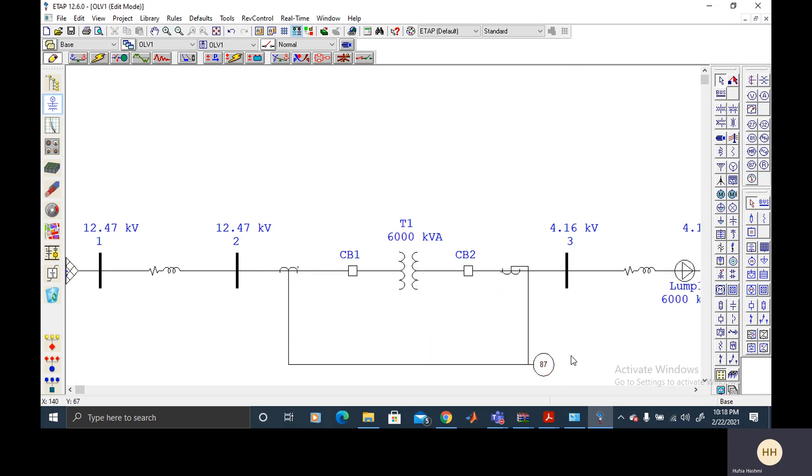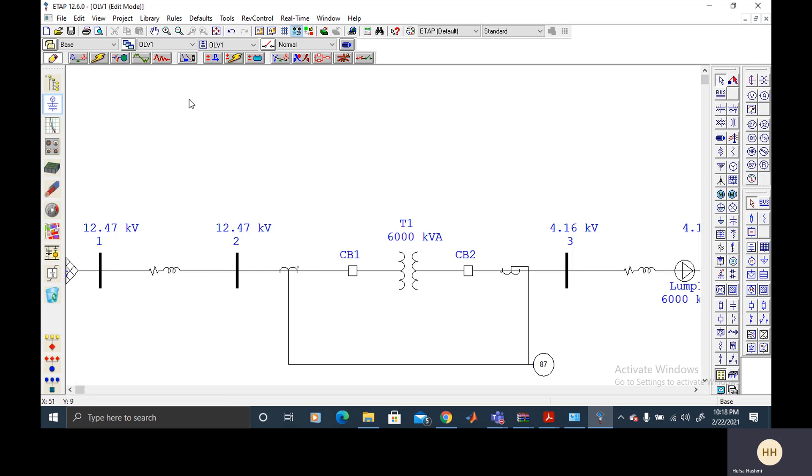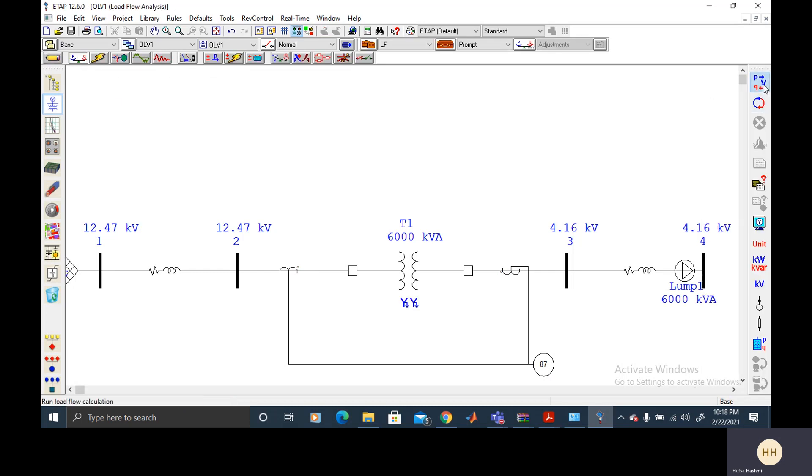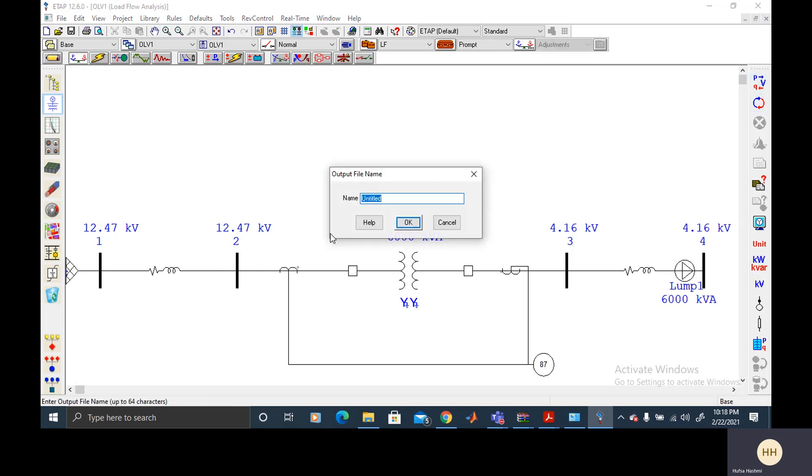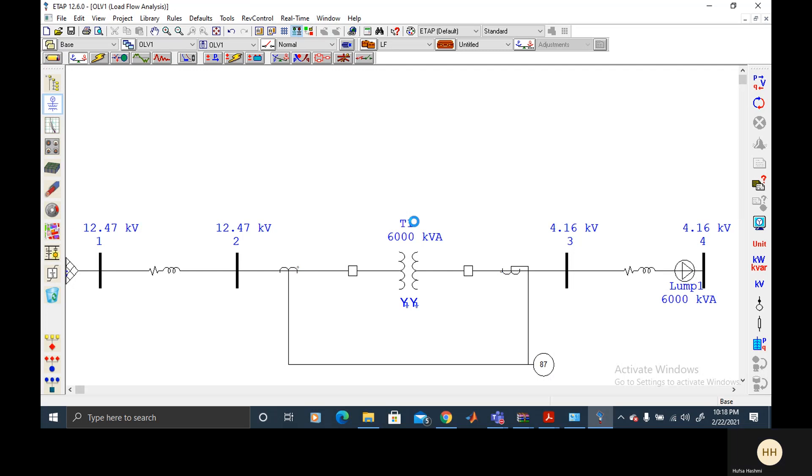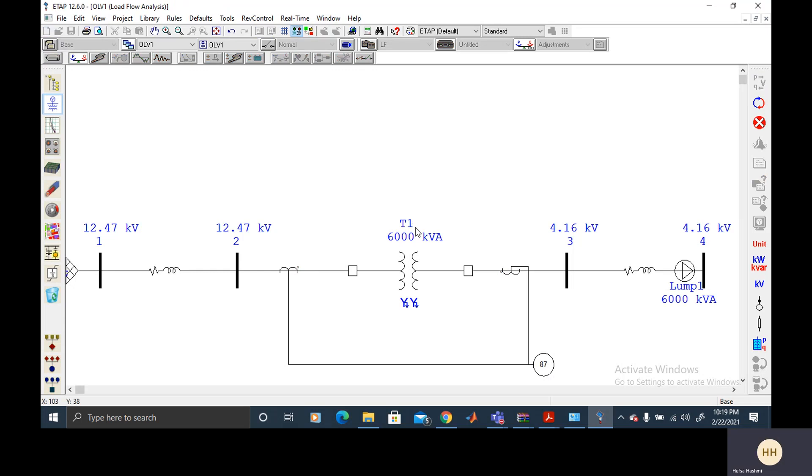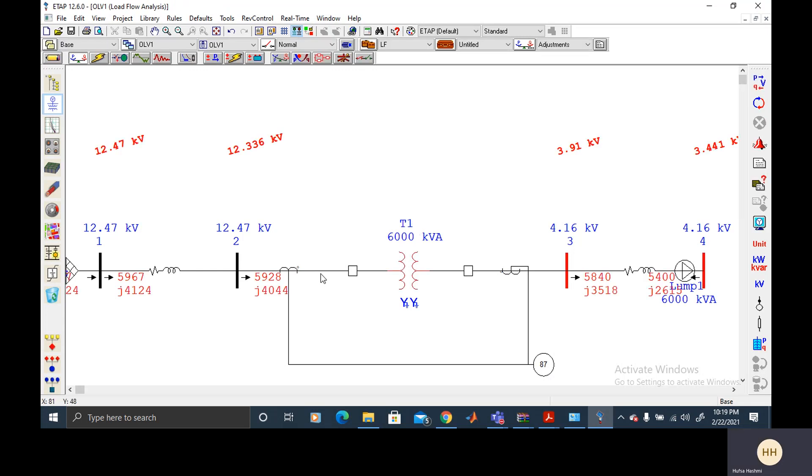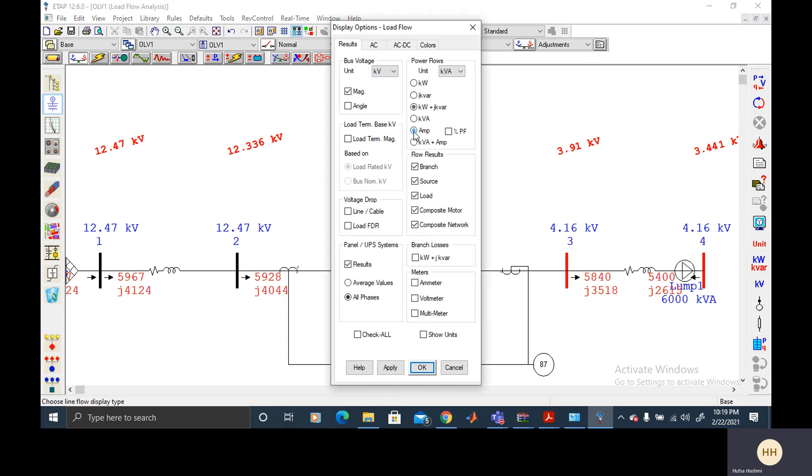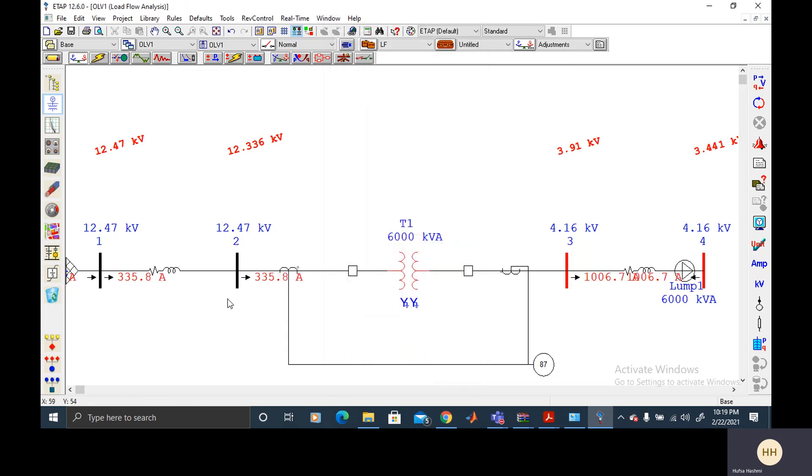And just in here and now we will do the load flow analysis to know the primary and secondary current, normal load flow currents. So we will do the load flow and I want to know the current. So I can change the settings here and I will select the ampere to show unit. So on the primary side I've got 335.8 ampere and then the secondary side it's almost 1010 ampere.